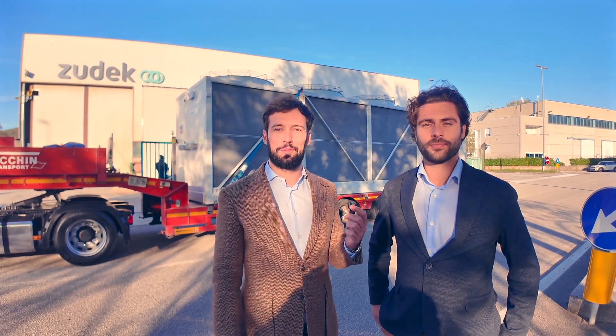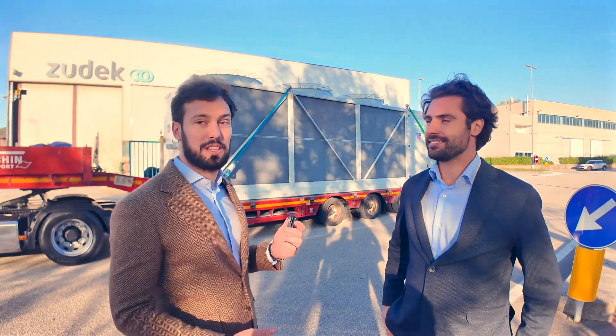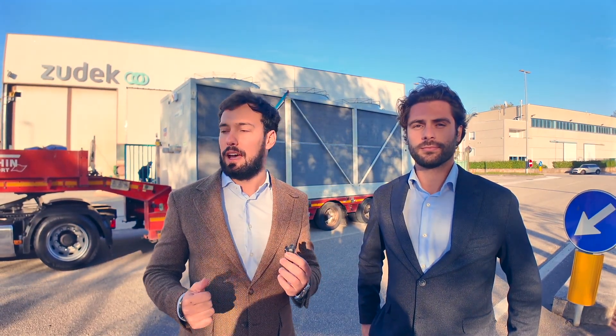I see that you've got a product ready to leave the Zudek facility for a customer in Switzerland. Tell us a little bit about this — this is what you call the Airmatic. What is so special about this product line? So this is the Airmatic — it's an air-cooled ammonia chiller. The specialty of the Airmatic is of course air cooling: it doesn't use water for condensing. It has an extremely low ammonia charge — 37 kilos for 350 kilowatt cooling. This product line has existed since 2008. We were the first to implement air-cooled technology on an ammonia chiller in Europe.